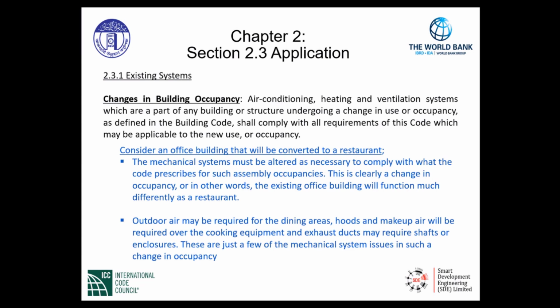The mechanical systems must be altered as necessary to comply with what the code prescribes for such assembly occupancies. This is clearly a change in occupancy, or in other words, the existing office building will function much differently as a restaurant. The restaurant is more densely populated in the dining room, whereas if you have an office building, we do not have such a dense population occurring in office buildings.